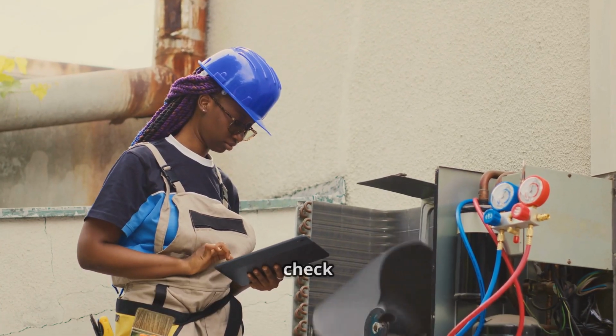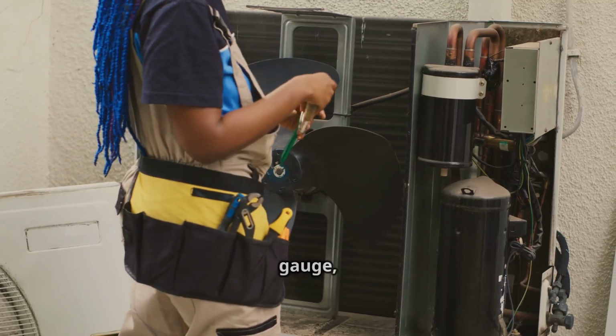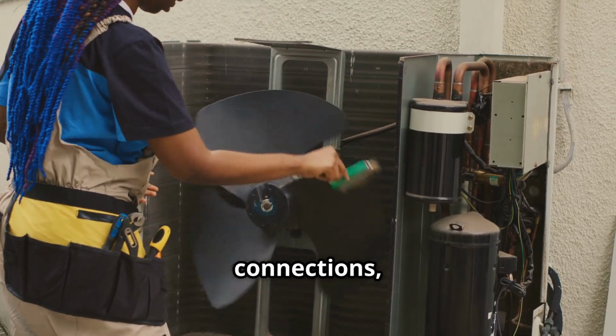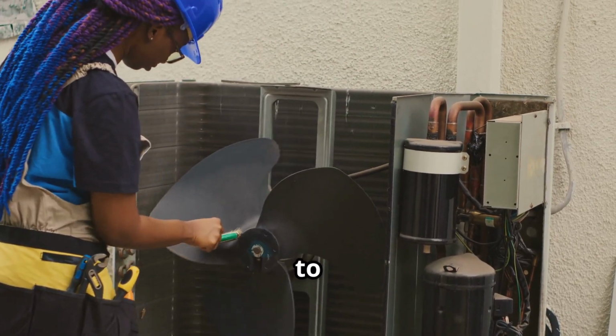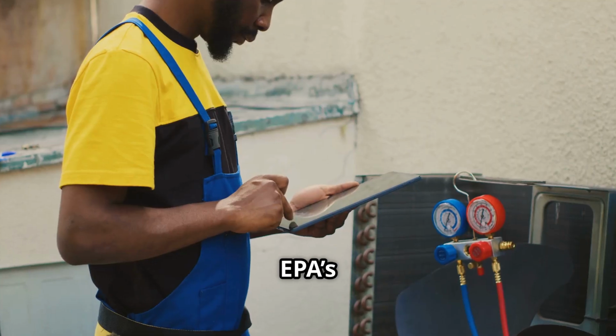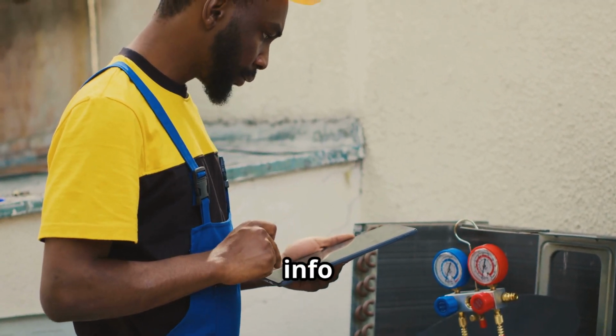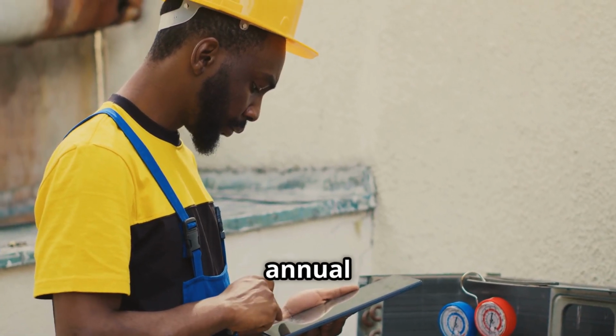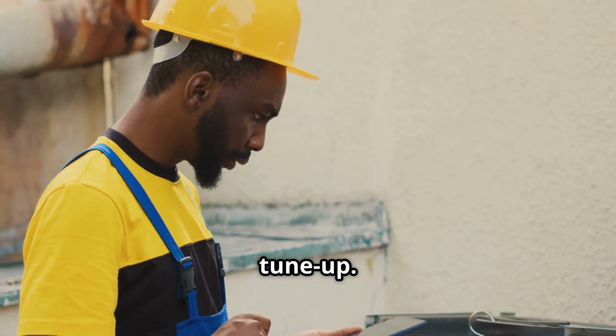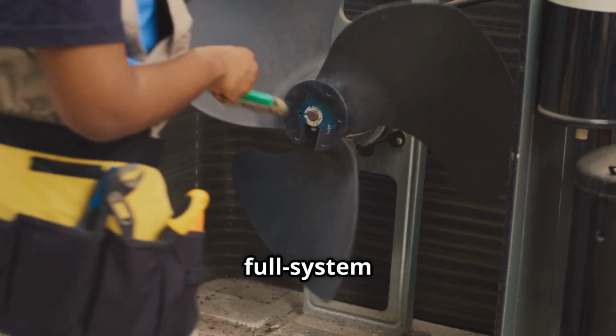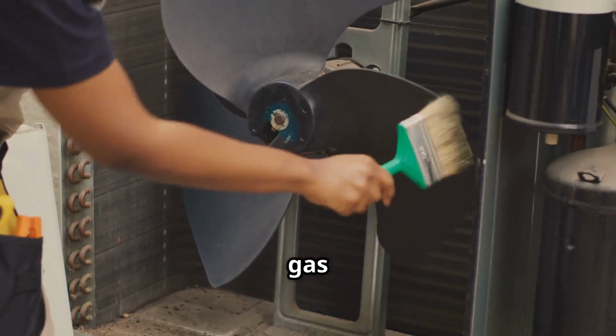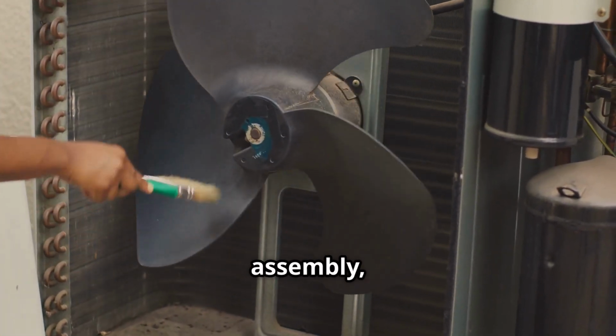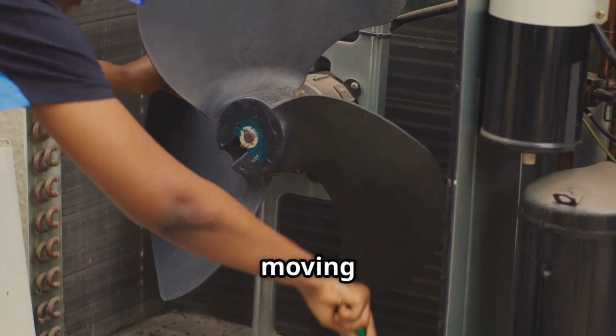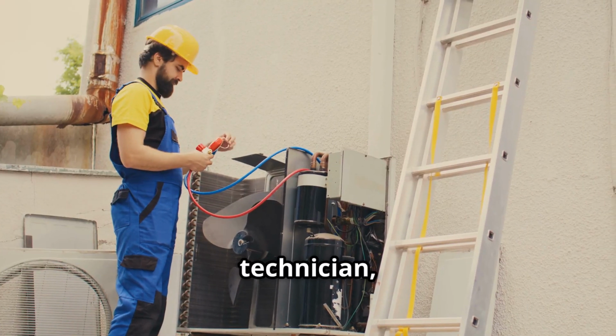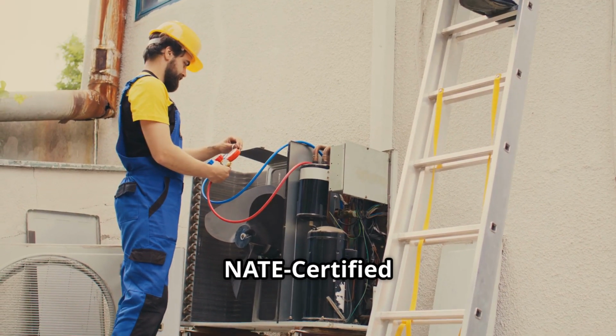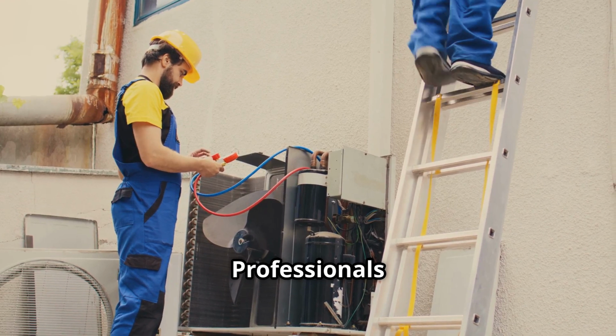Quarterly, it's crucial to check refrigerant levels using a digital gauge, inspect electrical connections, and examine drain lines to prevent clogs. The EPA's Refrigerant Handling Guide has all the info you need. And don't forget about an annual professional HVAC tune-up. This includes a full system performance test, checking for gas leaks, cleaning the blower assembly, and inspecting and lubricating moving parts. To find a certified technician, head over to the NATE Certified HVAC Professionals directory.